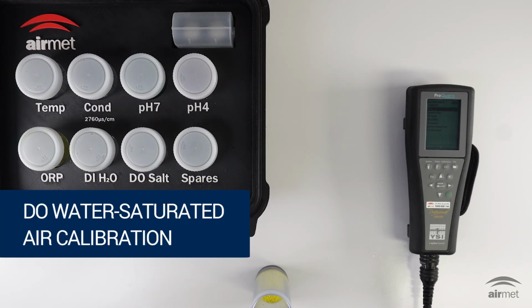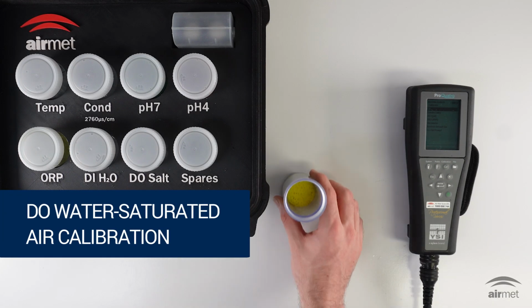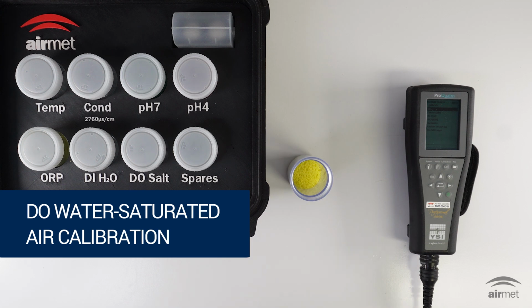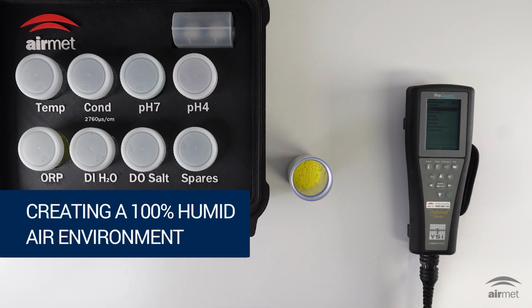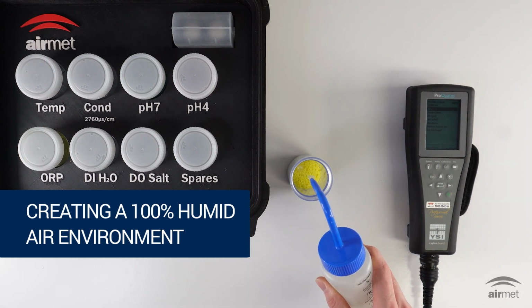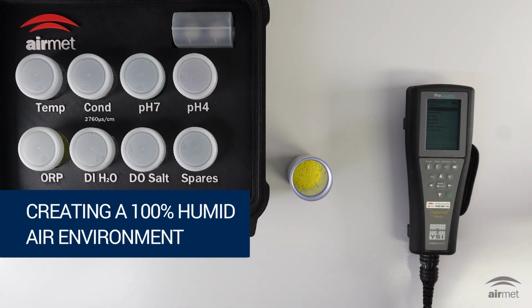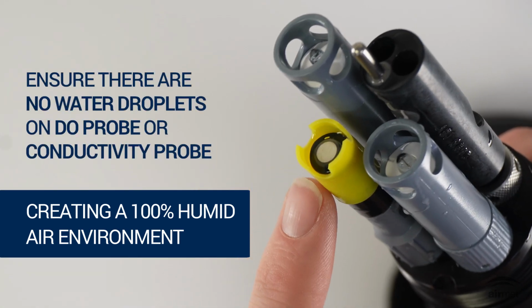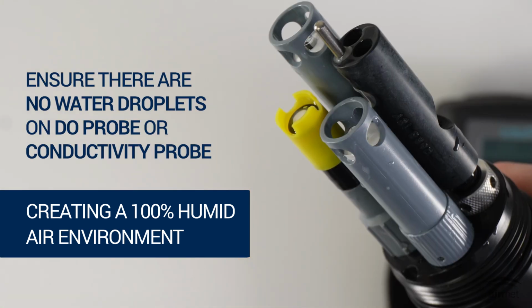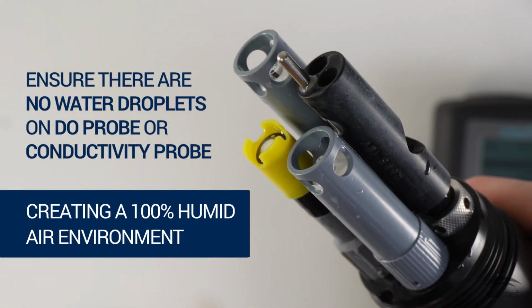A water-saturated air calibration is the most common and recommended method. It calibrates the sensor to 100% oxygen-saturated air, creating a 100% humid air environment. If needed, add a small amount of clean water to moisten the sponge inside the cup. Ensure there are no water droplets on the DO probe or the conductivity probe.